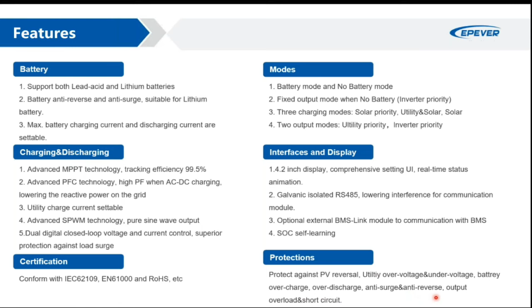Okay, let's see how this anti-surge function works. So we talked about limiting the surges in the current so that the lithium battery's BMS will not be activated and the power will continue. So there is a PTC element implemented on the positive junction of the battery with the low voltage converter side, actually. And PTC stands for positive temperature coefficient. PTC thermistors are resistors with a positive temperature coefficient, which means that the resistance will increase with increasing temperature.